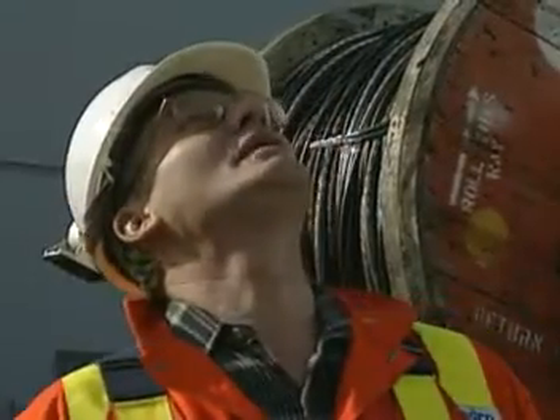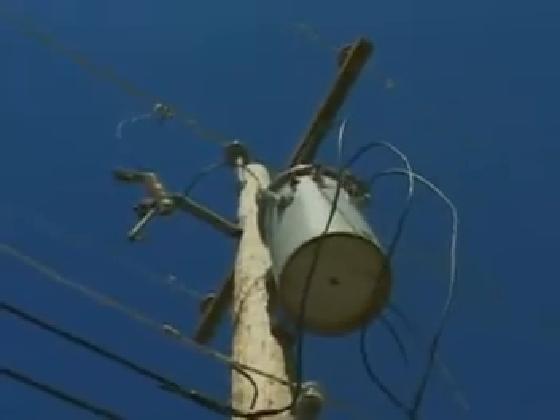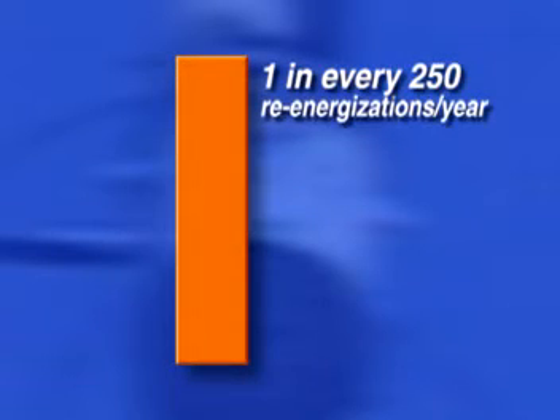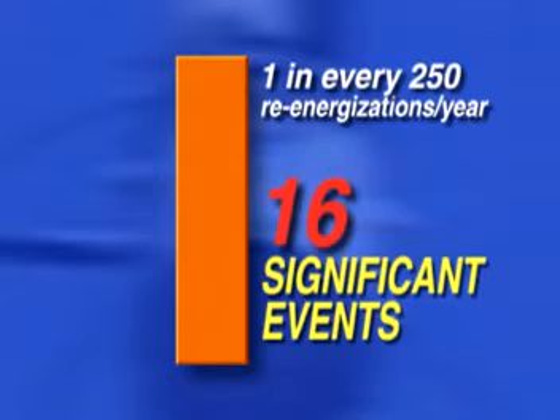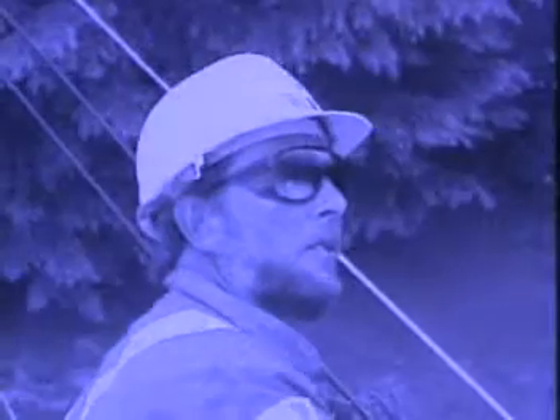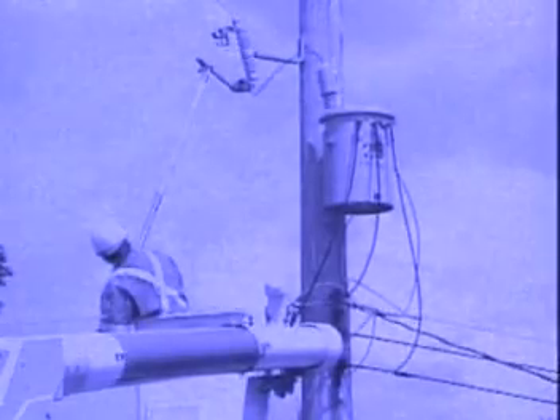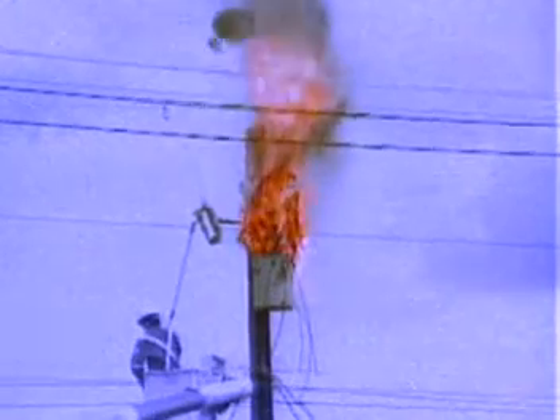Had IFDs been installed on these transformers, the line crews would have known immediately which transformers needed to be replaced due to internal faults. Furthermore, according to this utility's statistics, 1 in every 250, or in this case 16 of these transformers, could rupture or explode in 1 year. To reduce the risk of significant events, utilities have developed thorough but time-consuming procedures. Unfortunately, these procedures are not always followed because of the need to restore power quickly.